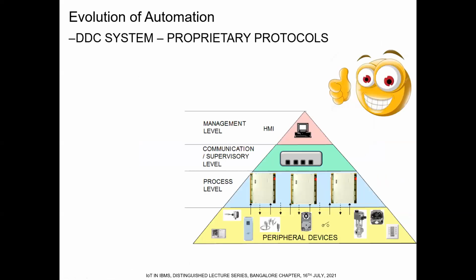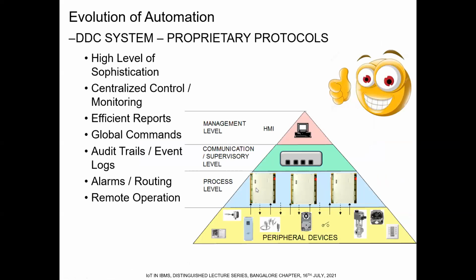And then we came to what is called the DDC system, the direct digital control. This was multi-processing. You can see here, these are electronic devices. A lot of algorithms could be written here. In a single controller, you could do multiple levels of automation. A temperature and a humidity sensor could both dictate. That means a dehumidification demand or a cooling demand could both dictate the movement of a single control valve, because you can write if, then, and so on and so forth into the processors here. These were DDC systems, which had a high level of sophistication.